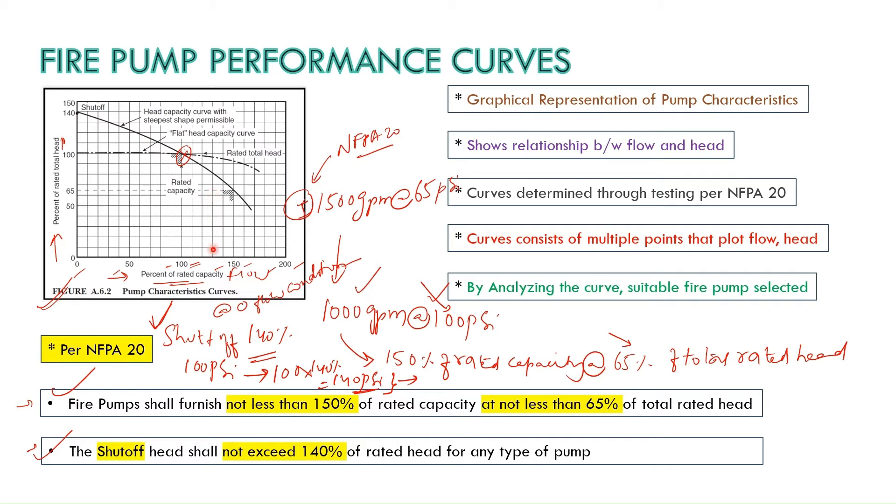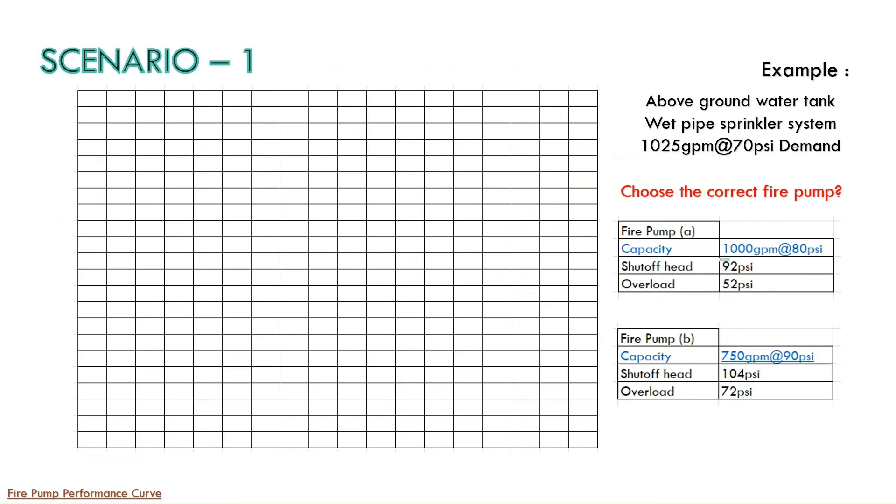This is the most important slide to be discussed in order to select the proper fire pump. So you need to watch the full video from here. So you have an example shown on your screen. We have the wet pipe sprinkler system installed in this particular project and the system demand based on the hydraulic calculation is 1025 GPM at 70 PSI.